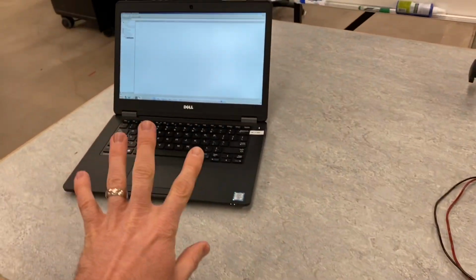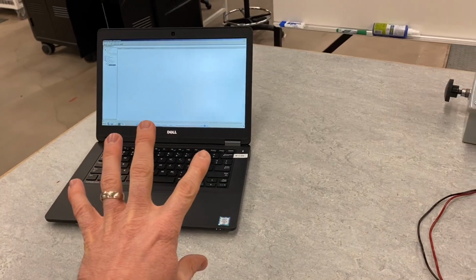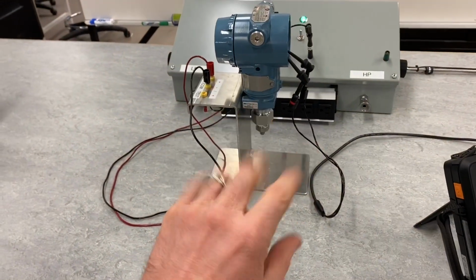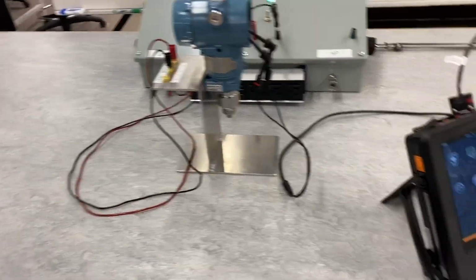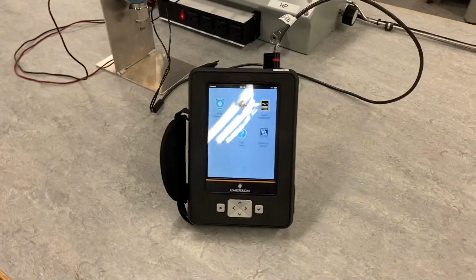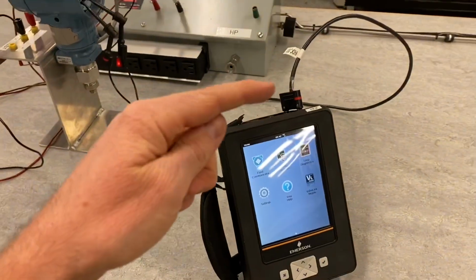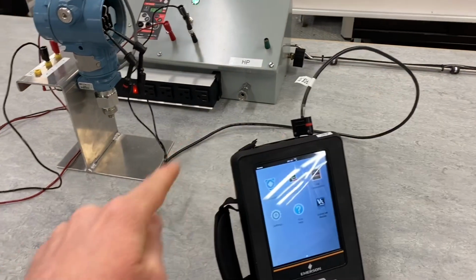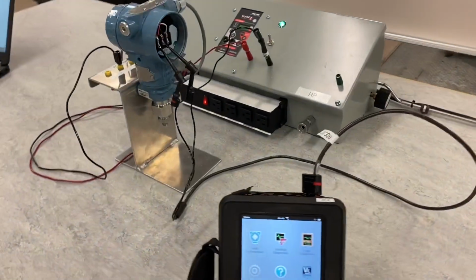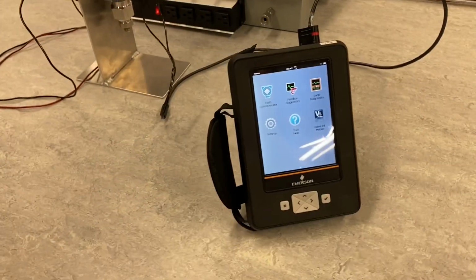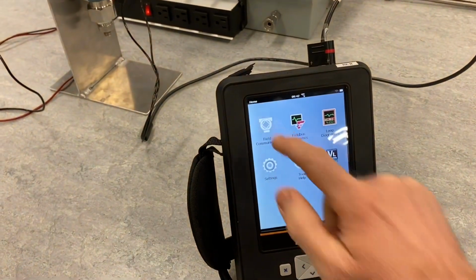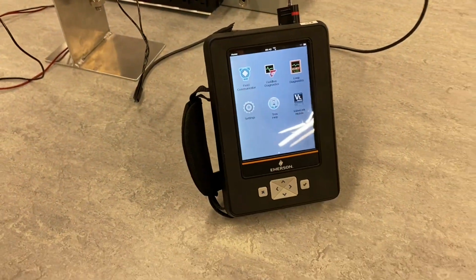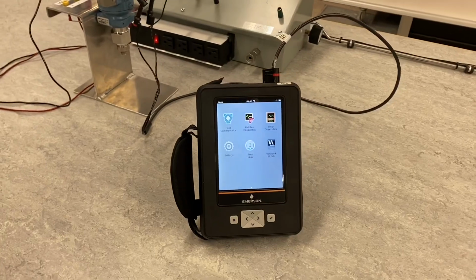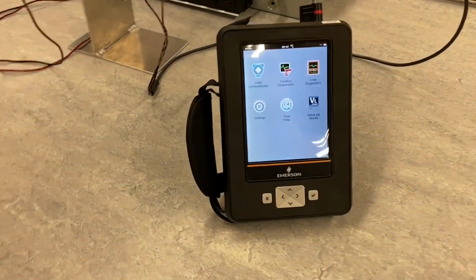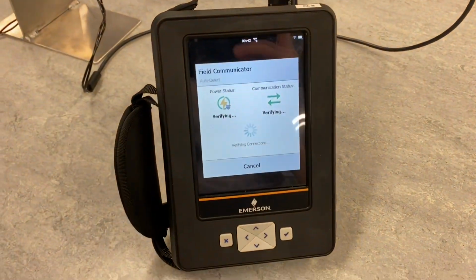So we can now pretend like the device here is offline, and we're doing some work on it remotely, and we're using our Trex communicator to do that. So I've got the Trex communicator, the hook lead cable here connected to the back of the transmitter, and I'm about to communicate with it. I'll just click on field communicator here. The transmitter is still powered on, and you can see it's searching for the device here.